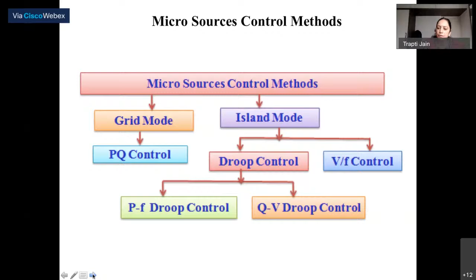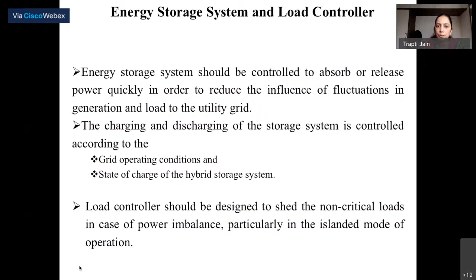Okay. So we have this energy system and load controllers. We should design the control strategies which allow the energy storage systems to absorb or release power quickly, so that the influence of temporary mismatches of power balance can be reduced in the microgrid. Basically, we need to control the charging and discharging of the storage system, which will depend upon the grid operating conditions and the state of charge of the hybrid storage system. And the load controller should be designed to shed the non-critical loads in case of power imbalance, particularly in the islanded mode of operation. You must be understanding that the main issue comes when the microgrid is operating in the islanded mode.